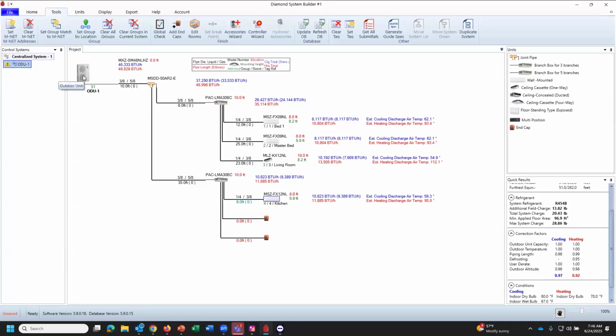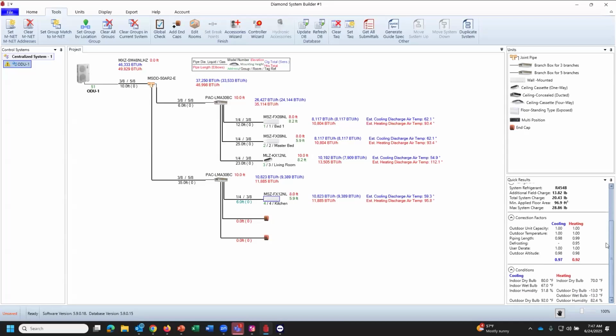If you've installed any of these outdoor units, they come from the factory just charged with enough refrigerant to basically fill this system. So what we're adding here is the refrigerant for the entirety of the system. So that gives us a total charge of 20.43 pounds. The floor area, we have actually looked at all of that as we went through. So we're actually only going to get about a 0.970 rate, which is pretty darn good.